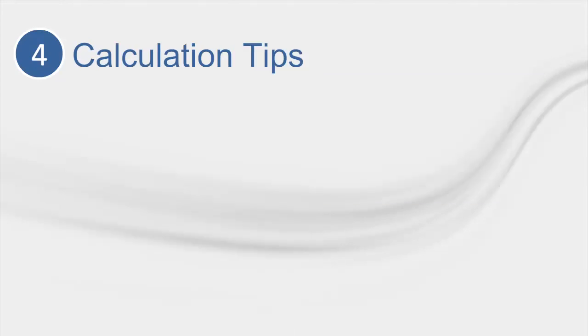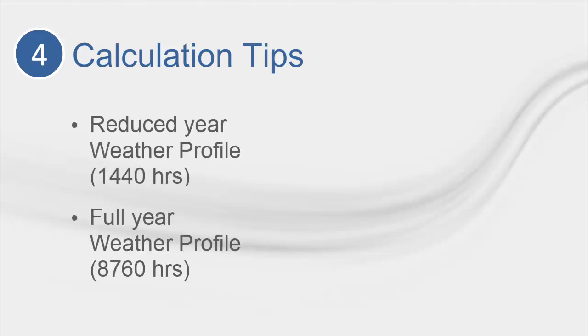For tip number four, we're going to talk about calculation tips. Before doing a detailed analysis, it is recommended that you run your model in reduced year mode. Running a model in full year mode will increase the calculation time by up to five times the typical run time. Running in reduced year mode will allow you to flush out any large issues with as little run time as possible. Once you refine your model, run in full year mode to satisfy LEED and any other bodies that will require you to run an energy model with a full year profile.